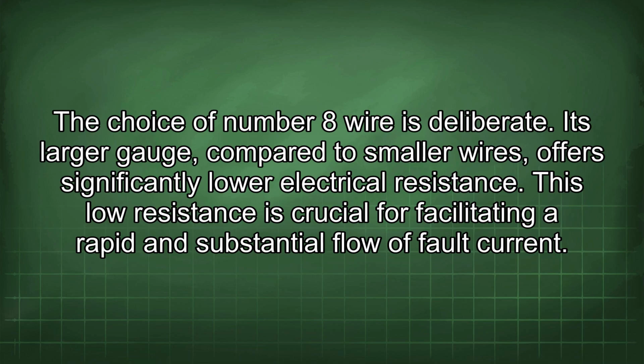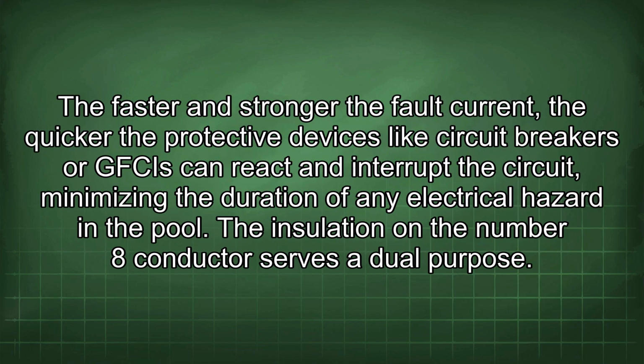The choice of number 8 wire is deliberate. Its larger gauge, compared to smaller wires, offers significantly lower electrical resistance. This low resistance is crucial for facilitating a rapid and substantial flow of fault current. The faster and stronger the fault current, the quicker the protective devices like circuit breakers or GFCIs can react and interrupt the circuit, minimizing the duration of any electrical hazard in the pool.